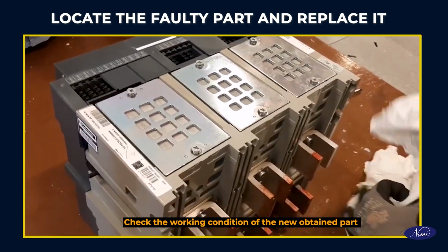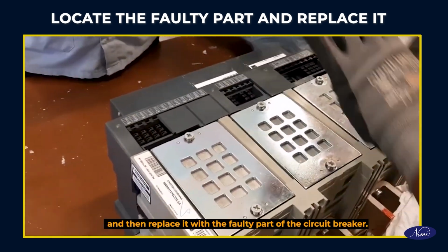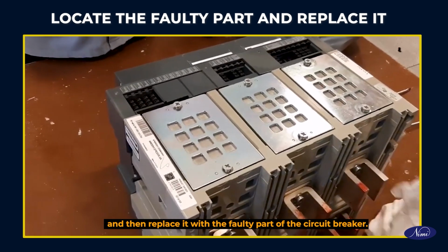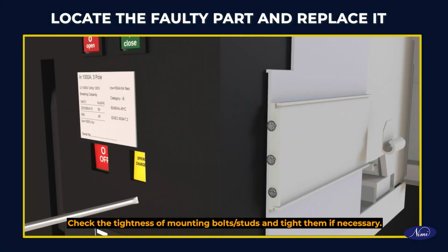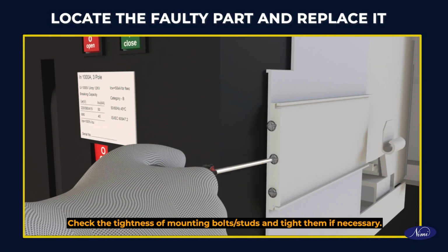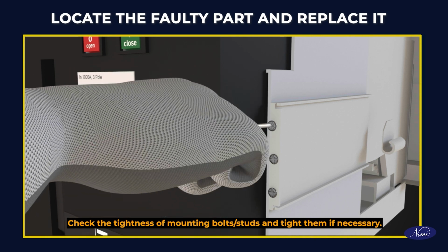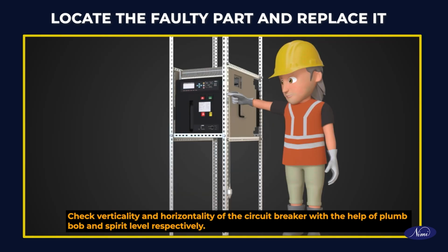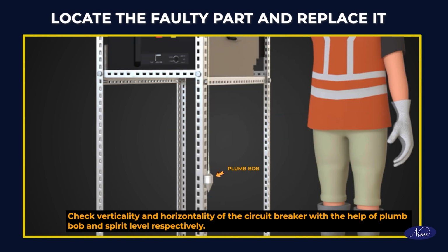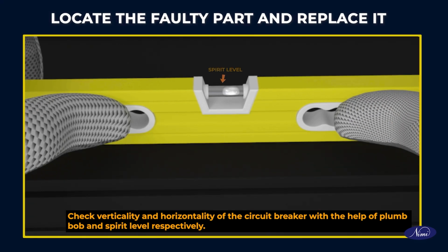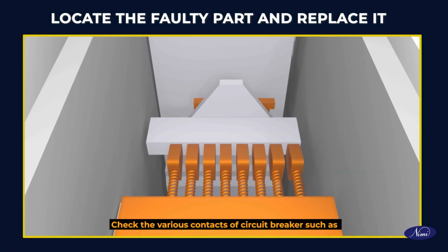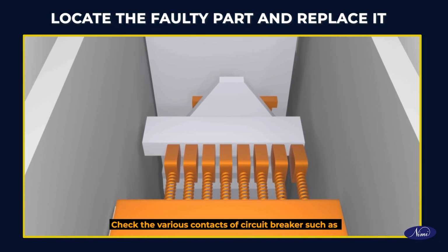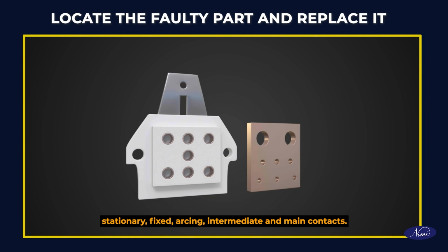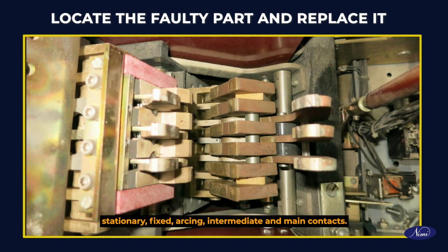Check the working condition of the newly obtained part and then replace it with the faulty part of the circuit breaker. Check the tightness of mounting bolts or studs and tighten them if necessary. Check verticality and horizontality of the circuit breaker with the help of plumb bob and spirit level respectively. Check the various contacts of circuit breaker such as stationary, fixed, arcing, intermediate and main contacts.